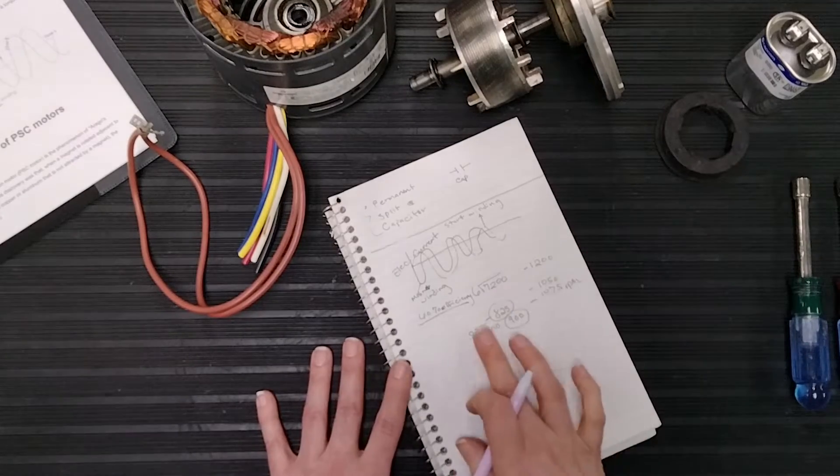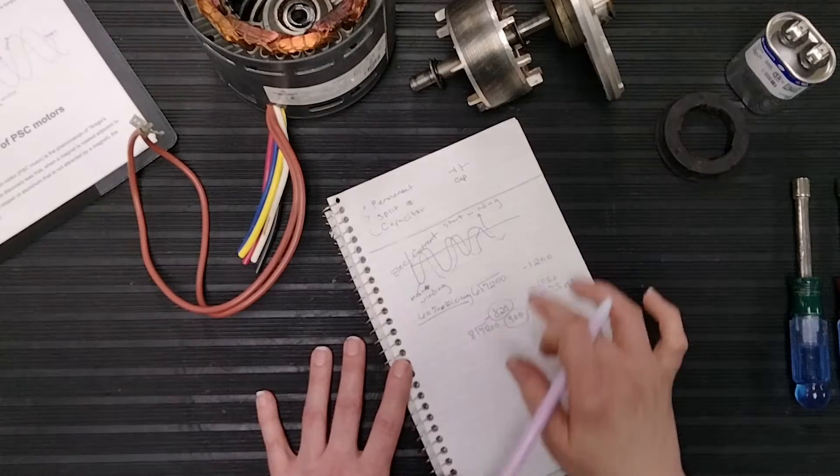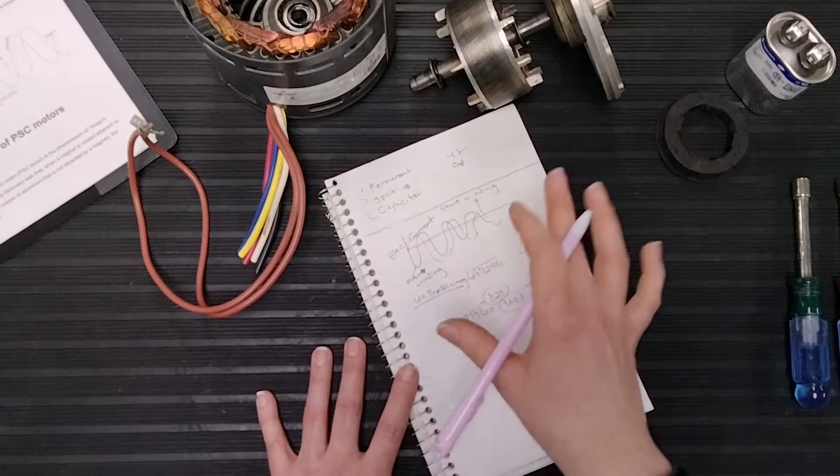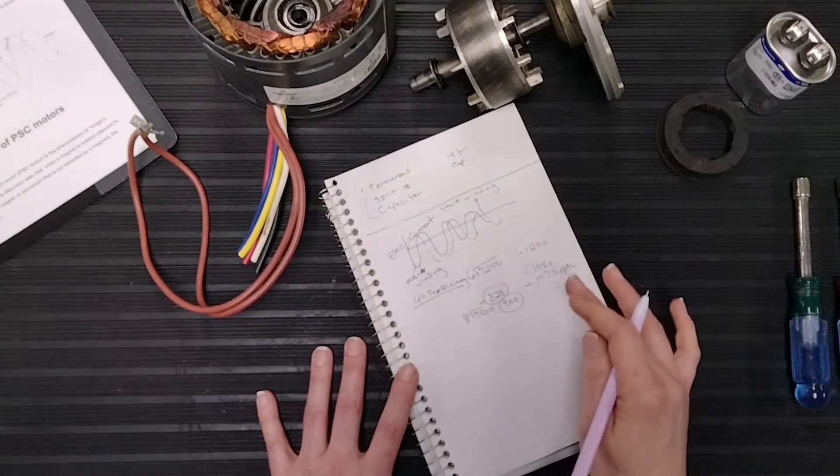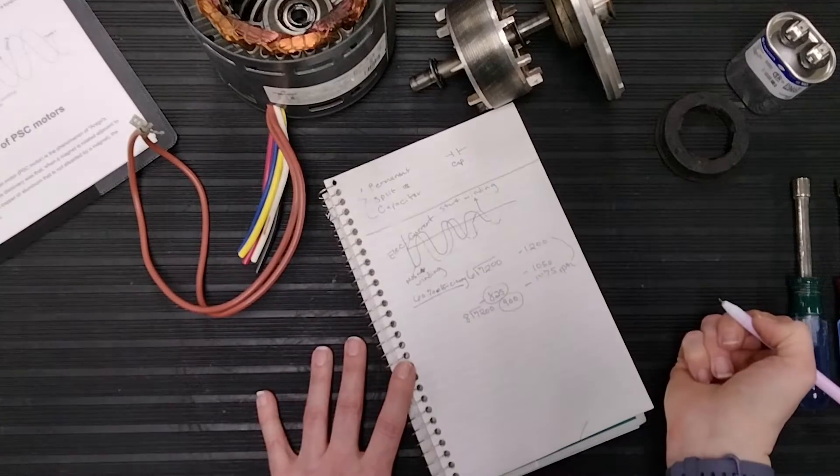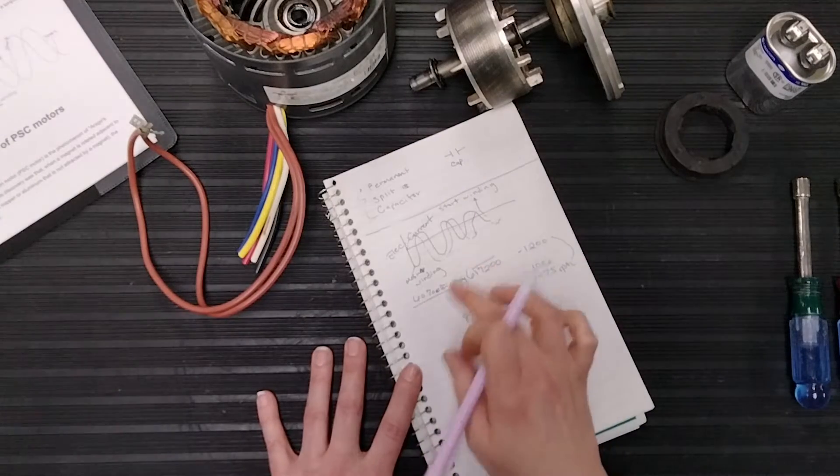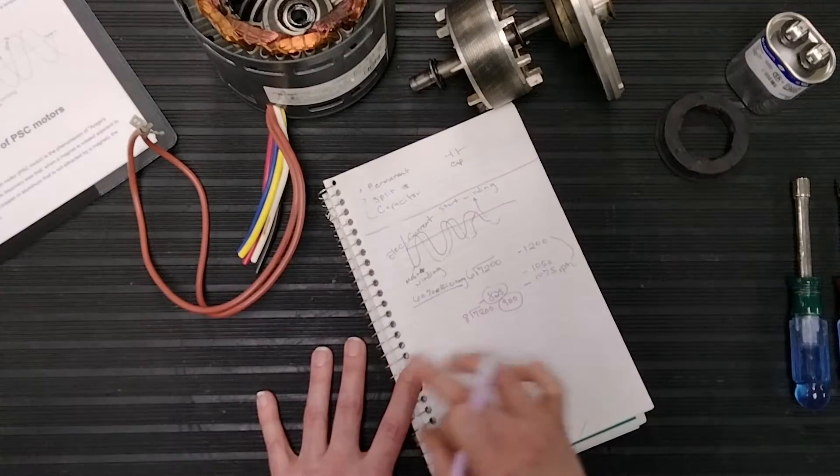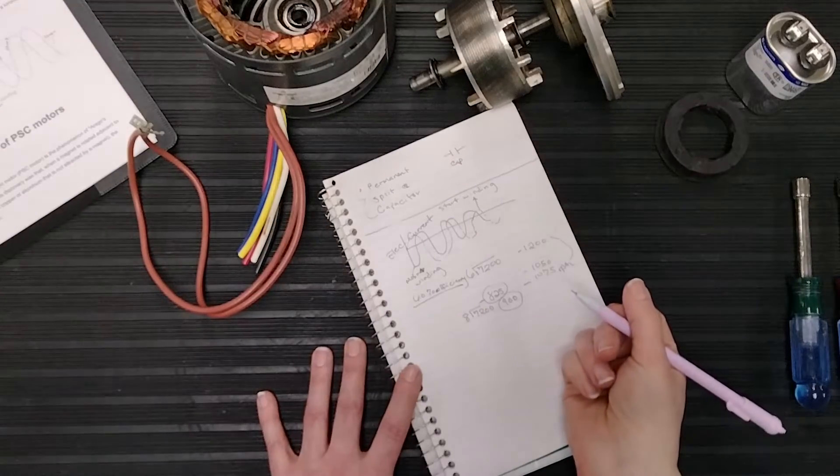What else could happen when we replace that with that 1200 RPM motor? Well, it has a fan blade, or a blower wheel, that is placed on there, designed for this RPM. So if we place the wrong RPM on that, now we've messed up the blower wheel, or the fan blade, from what it was originally designed to run on.